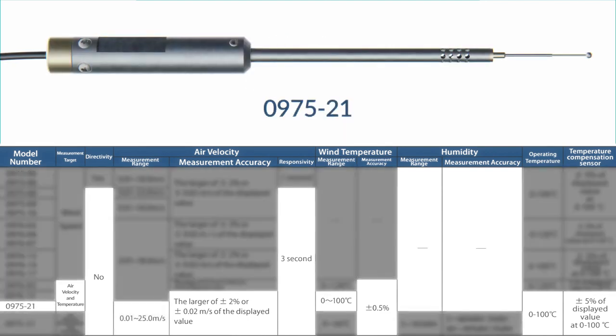Model 0975-21 is another omnidirectional needle-type probe, but this one is capable of measuring temperature along with air velocity. Air velocity is measured within 0.01 to 25.0 meters per second to the larger of ±2% or ±0.02 meters per second of the displayed value every 3 seconds. Temperature can be measured from 0 to 100 degrees Celsius with an accuracy of ±0.5%.